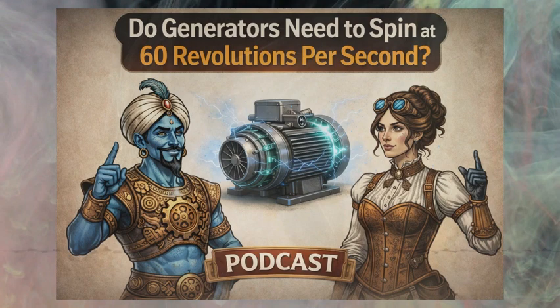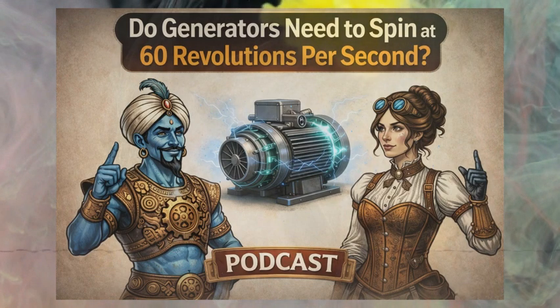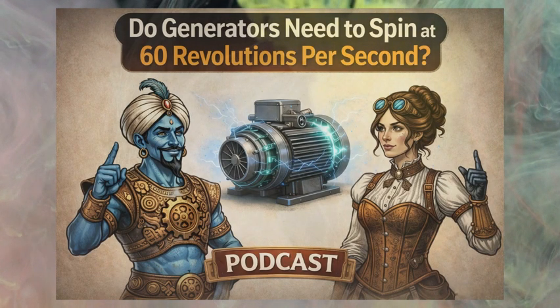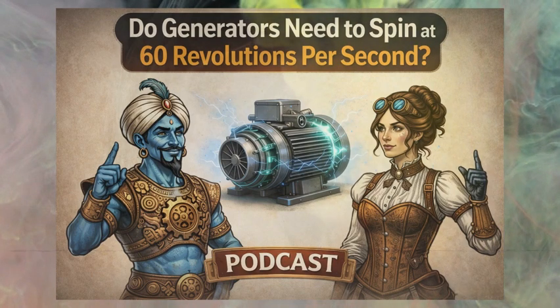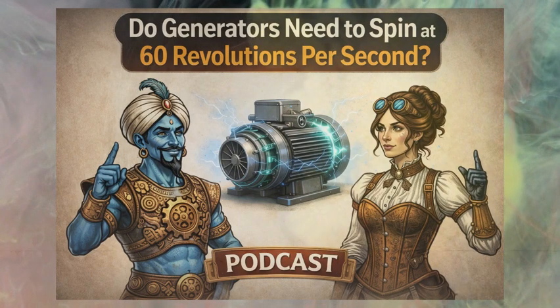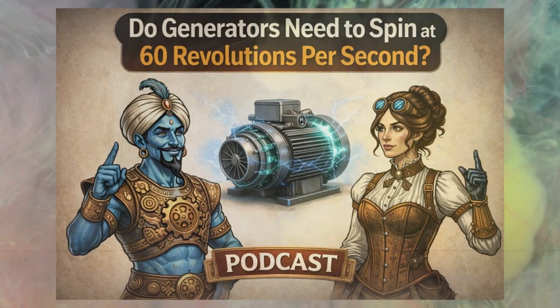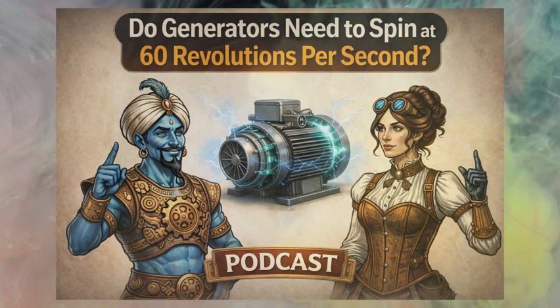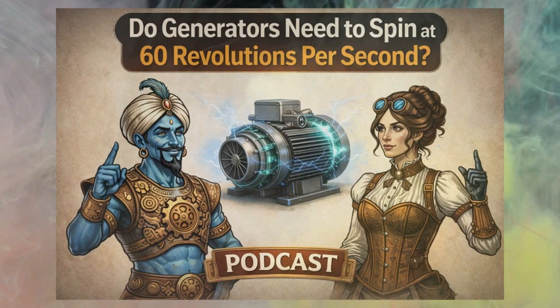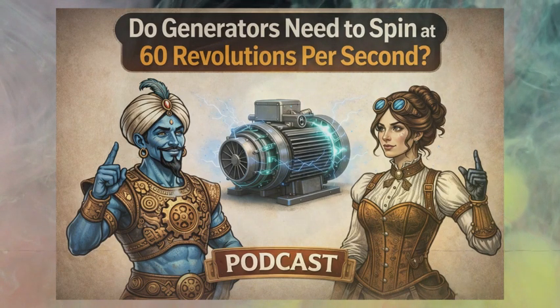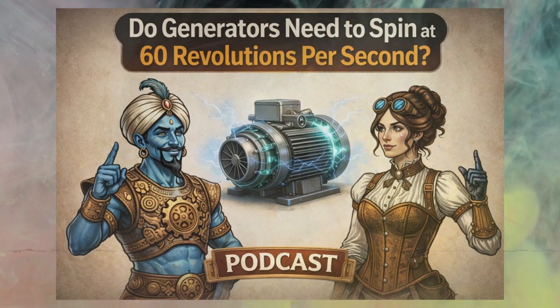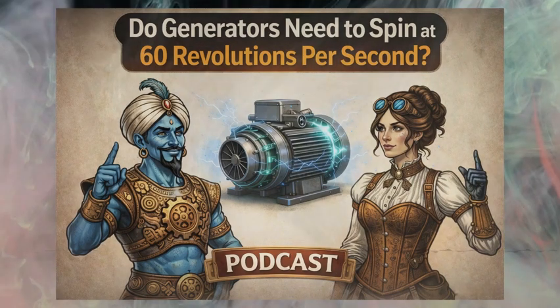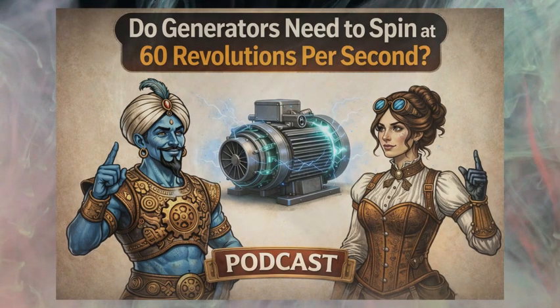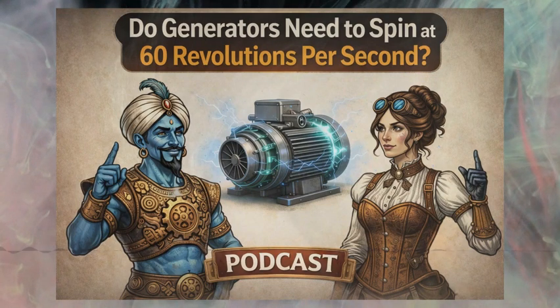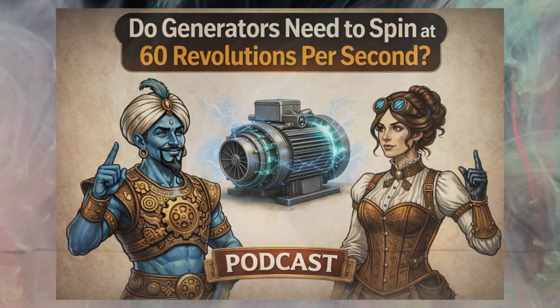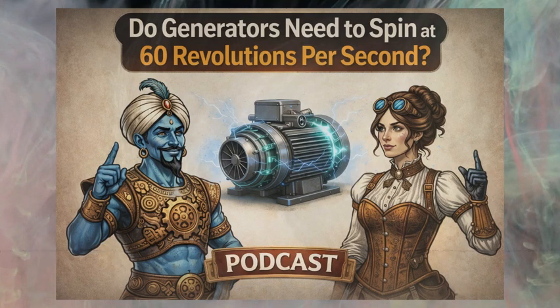So to pull it all together, that paradox we started with, the slow generator making high-frequency power, it's solved entirely by the clever engineering of the magnetic field. The secret to getting a stable 60 hertz, whether your engine is a 3600 RPM turbine or a 90 RPM water wheel, is just building the rotor with the right number of magnetic poles. The generator becomes a translator, converting mechanical speed into a fixed number of electrical cycles, with the pole count as the dictionary. It's just a beautiful example of how a rigid standard forces these incredibly elegant engineering solutions.